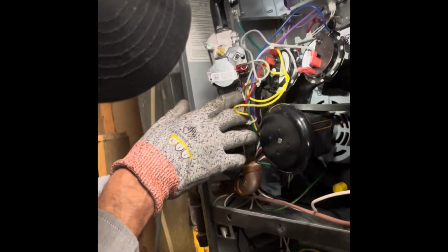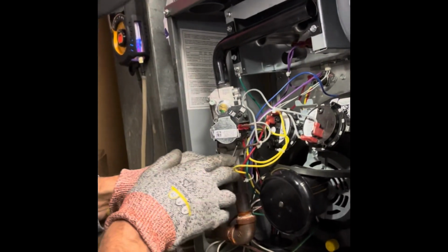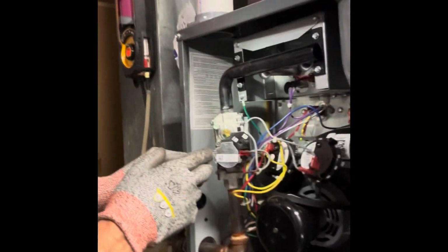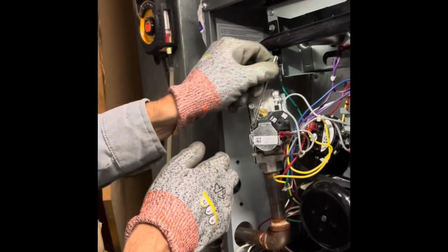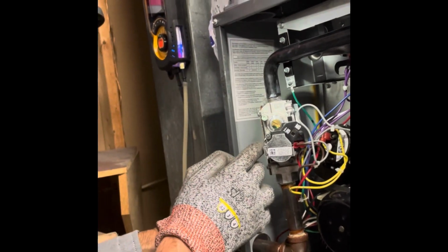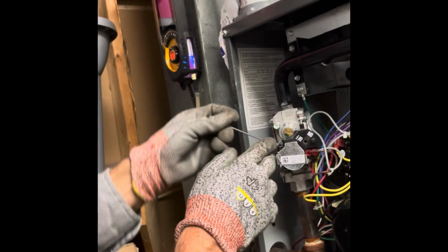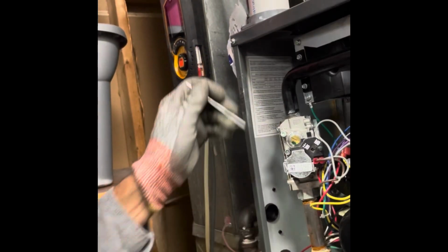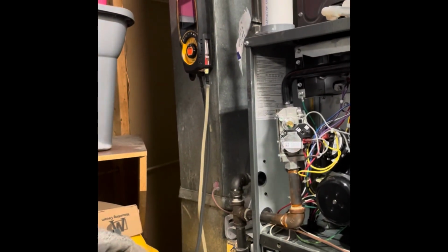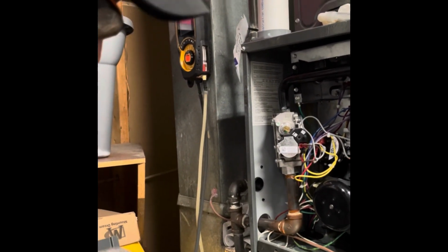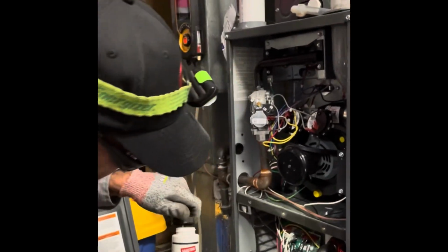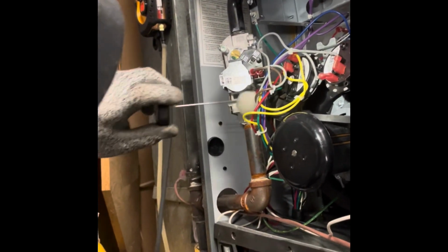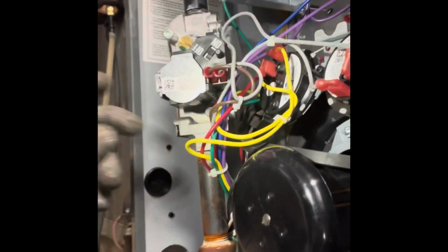I'm going to double check the street pressure one. Turn it right to tighten it, left to loosen. And up here, this one is loose because I just checked gas pressure. Very important that these things get tightened up. You want to soap test them, make sure nothing's leaking. And then what I'll do is a quick leak test once the burner is lit on that port I've tapped into. As for the other port, sorry about getting in front of the camera there, I can soap this one up now. This one's street pressure, which has gas going through this little fitting. So if I was leaking gas, it's going to blow up bubbles.